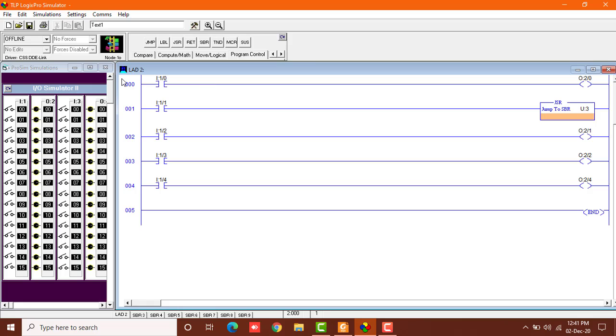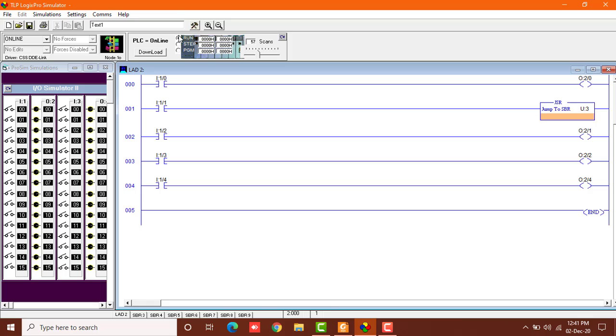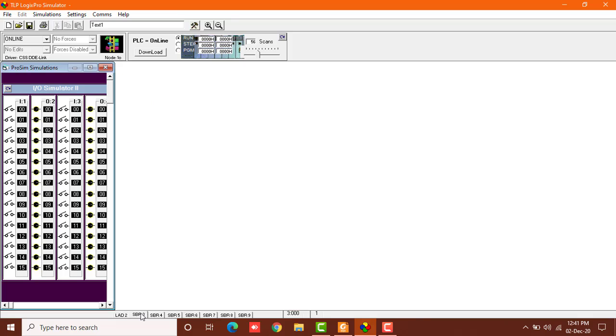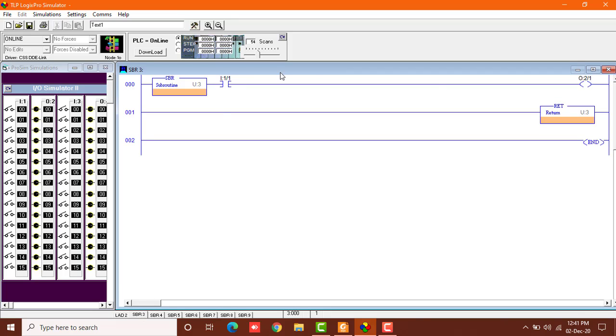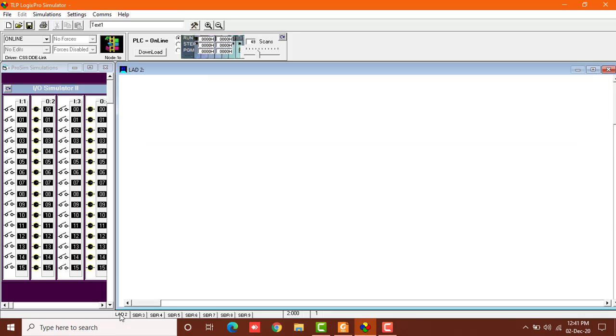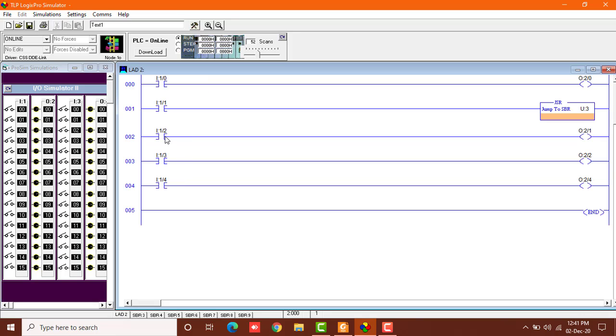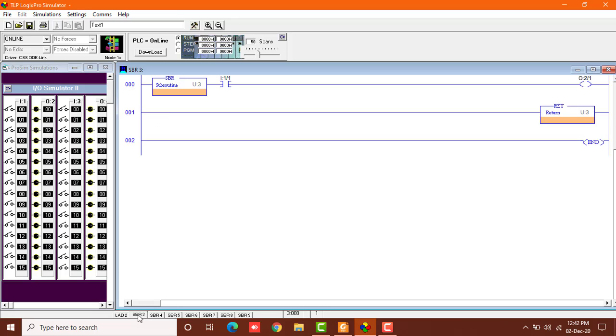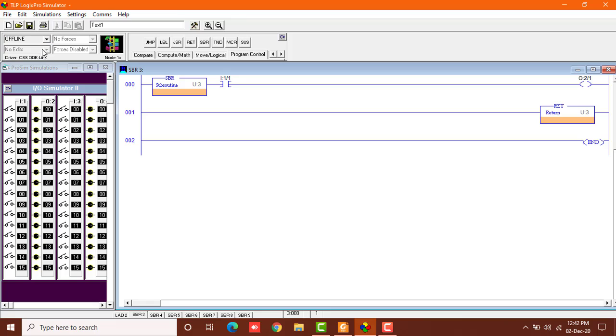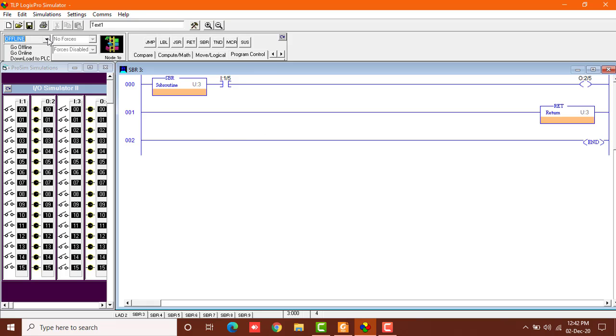So I've downloaded it to PLC. I'll go online and run this program. Now you can see our subroutine 3 has input 1 colon 1 and output 2 colon 1, and I have some mistake. I have used this input 1 colon 1 over here which I shouldn't have because I'm using this input 1 colon 1 over here too. So I'll turn it off and change these inputs to 1 colon 5 and this output to 2 colon 5. I'll download this to PLC again.